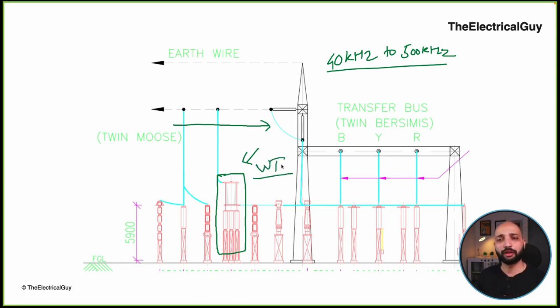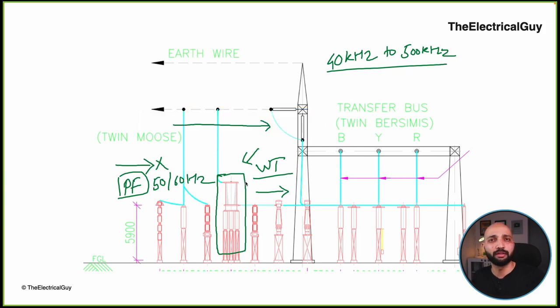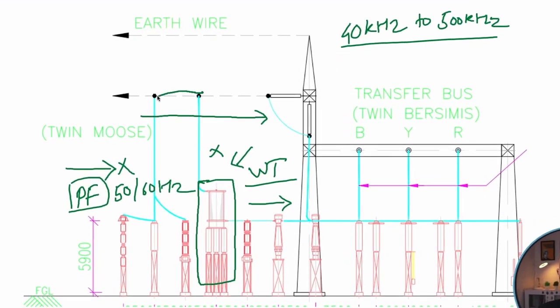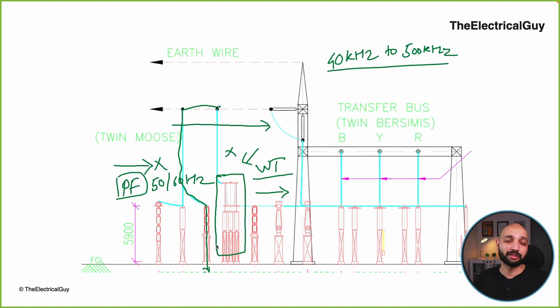Clear? Understood? What the wave trap does is simply block the high frequency signal. So if it senses 40 kilohertz or 500 kilohertz, it will block that particular signal, and it will only allow the signal which is at power frequency, which could be 50 hertz or 60 hertz. So it will only allow that signal to enter the substation, thereby protecting the equipment which may be impacted because of this high communication frequency. So basically a wave trap is nothing but a low pass filter which allows signals with low frequency and blocks signals with high frequency. When the signals are blocked by the wave trap, that high frequency signal will look for another path, which it will find via the CVT, because the CVT is offering it capacitance and it will flow through that capacitance.